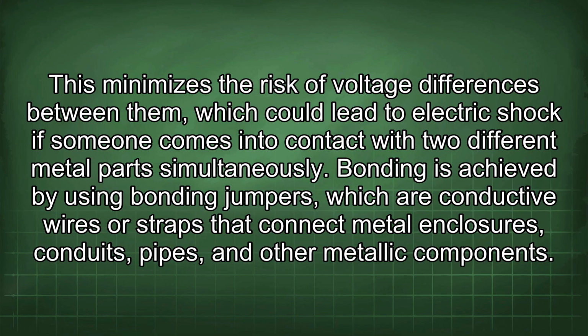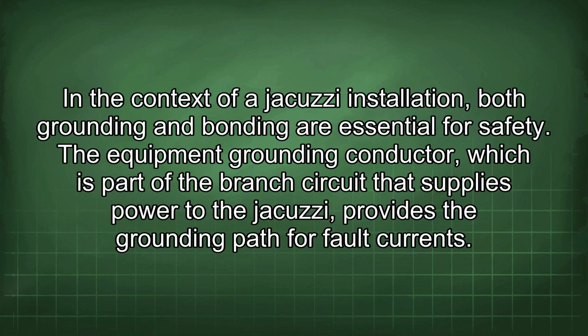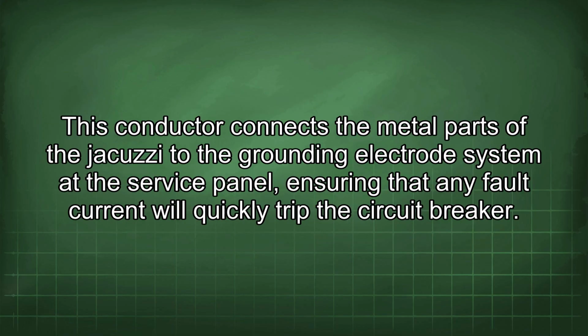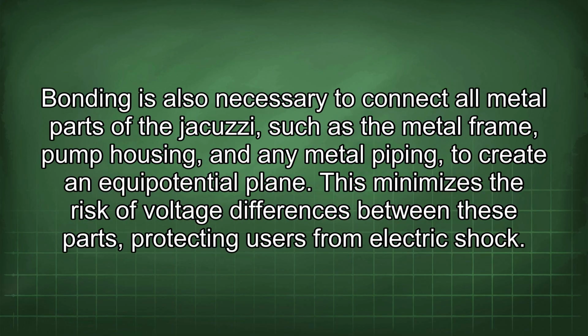In the context of a jacuzzi installation, both grounding and bonding are essential for safety. The equipment grounding conductor, which is part of the branch circuit that supplies power to the jacuzzi, provides the grounding path for fault currents. This conductor connects the metal parts of the jacuzzi to the grounding electrode system at the service panel, ensuring that any fault current will quickly trip the circuit breaker. Bonding is also necessary to connect all metal parts of the jacuzzi, such as the metal frame, pump housing, and any metal piping, to create an equipotential plane. This minimizes the risk of voltage differences between these parts, protecting users from electric shock.